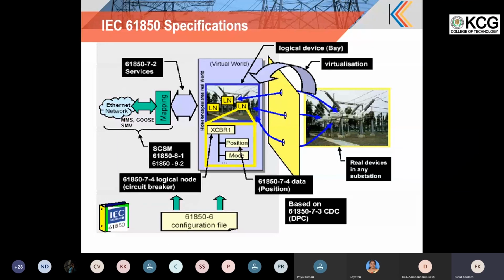So logical node comes in which standard? 7-4. 61850 7-4 deals with the logical node of the circuit breaker. Similar to circuit breaker, all the logical nodes are given under 7-4. And all the data elements under the logical node are defined under 7-3. It is nothing but common data classes. They are defined common data classes, associated with the multiple logical nodes and represented in the 7-3 and 7-4 standards.